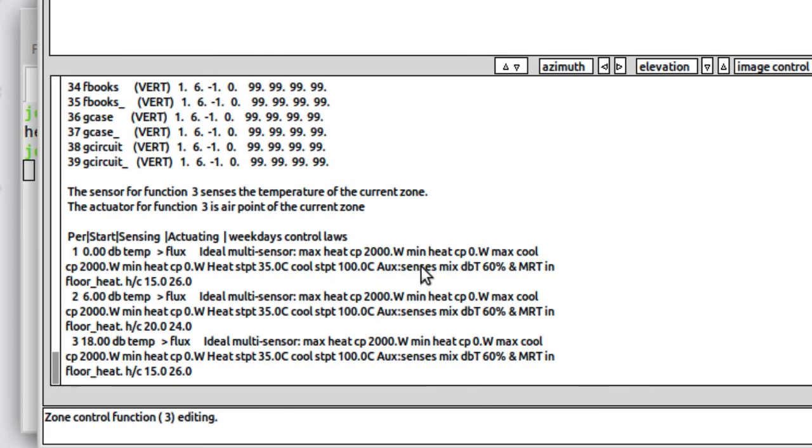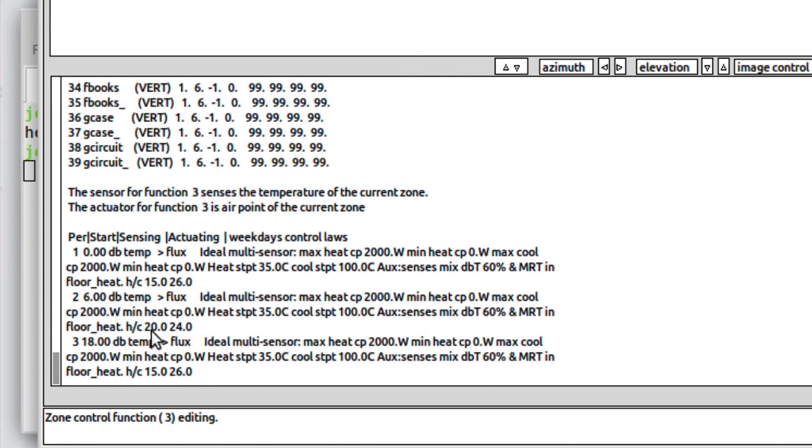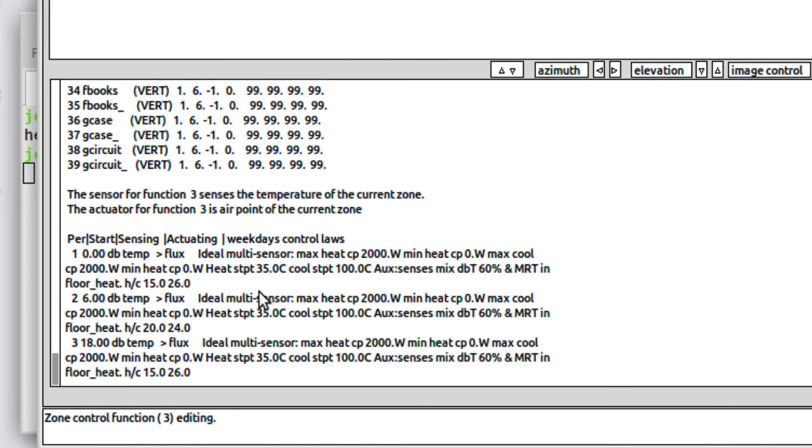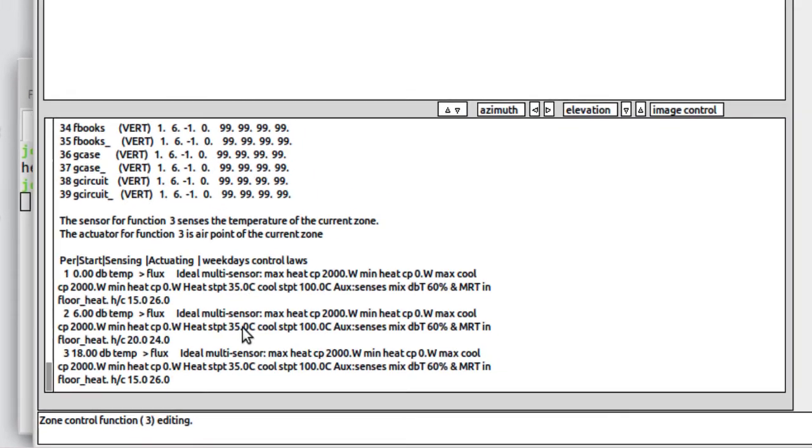What we're sensing in the room is a mix of dry bulb temperature, 60%, and the balance in mean radiant temperature. We want to maintain the room between early in the morning between 15 and 26 degrees. Later after six o'clock we want to maintain the room between 20 and 24 degrees. Then in the evening we go back to the set point. We allow the heating in the thin zone to get up to 35 degrees. That sets the working temperature of the fluid. So this is a low temperature heating system.